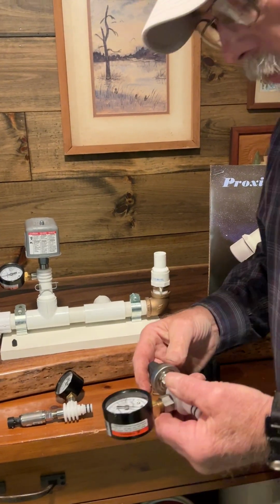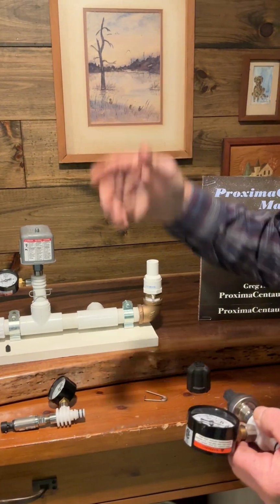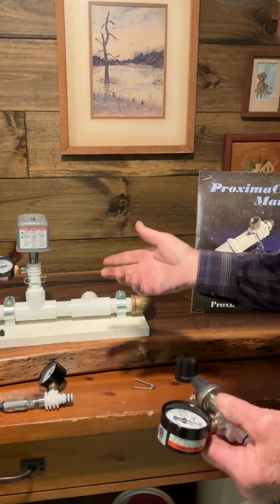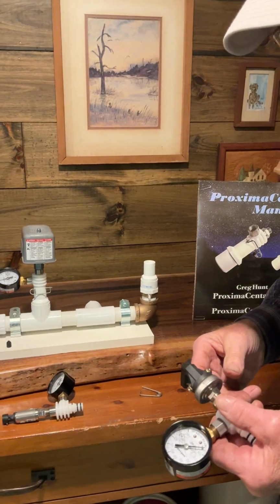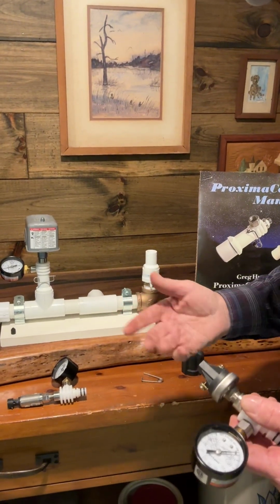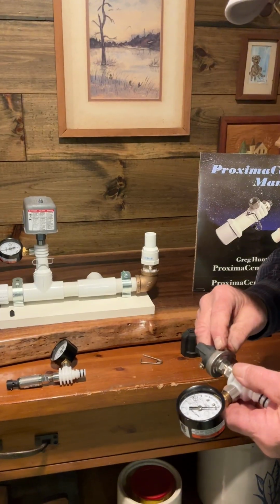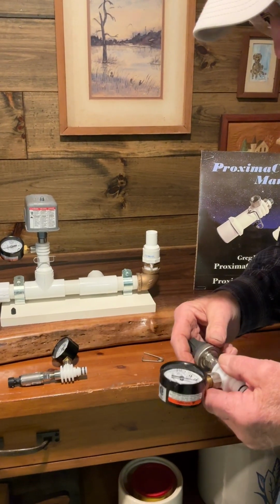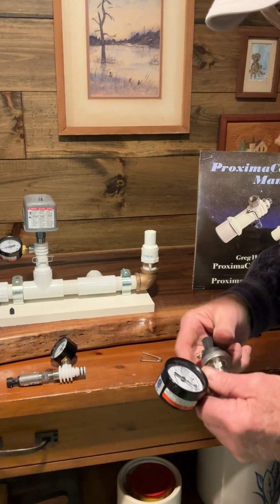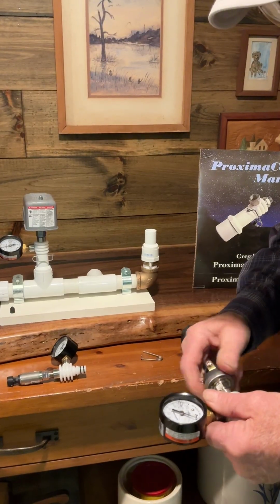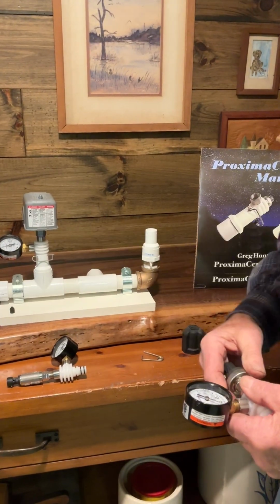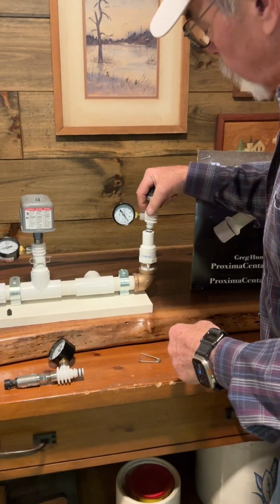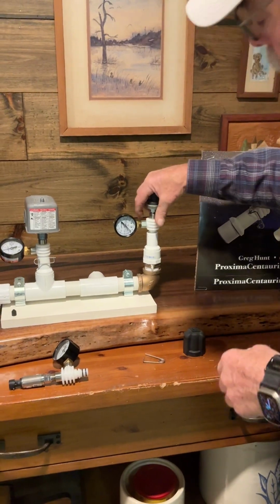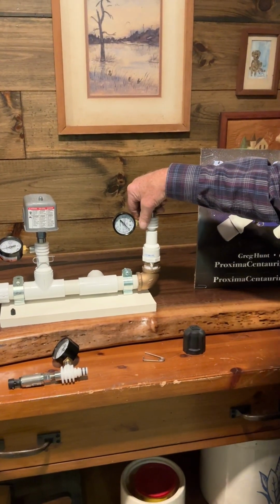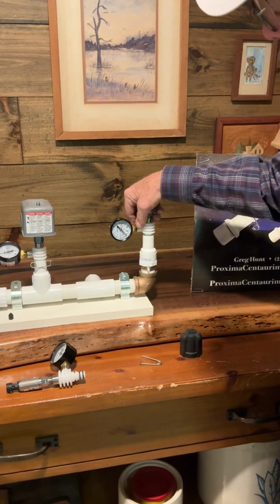We've all done this, where the drive's got some problems and you want to change the transducer or pressure sensor just to see if that's what the problem is, because sometimes these things have problems too. It's real easy: just undo your wires, unscrew that thing, stick a new one on. You haven't had to drain anything, and you can just plug it back in to try it and see if that solves your problem. It's so easy to do.